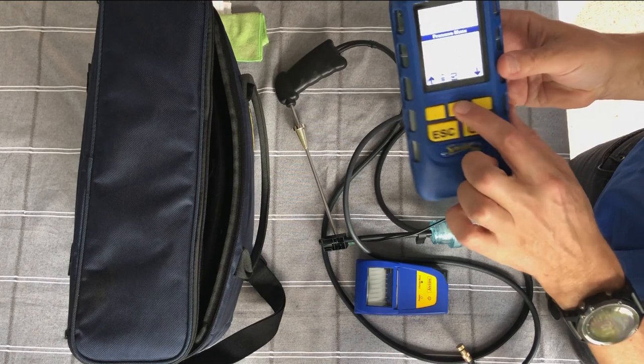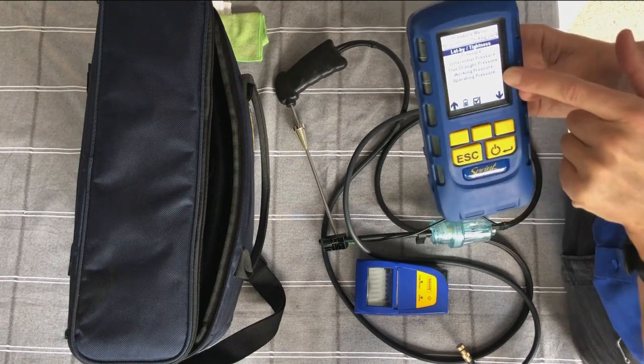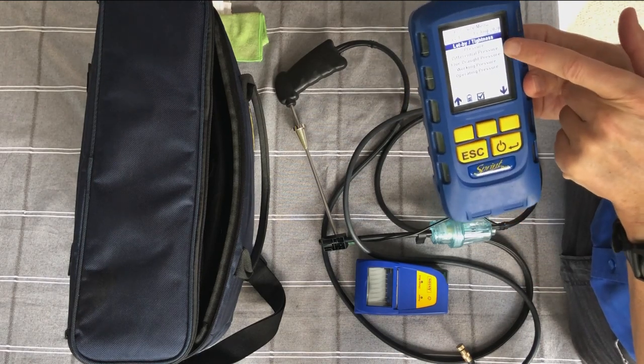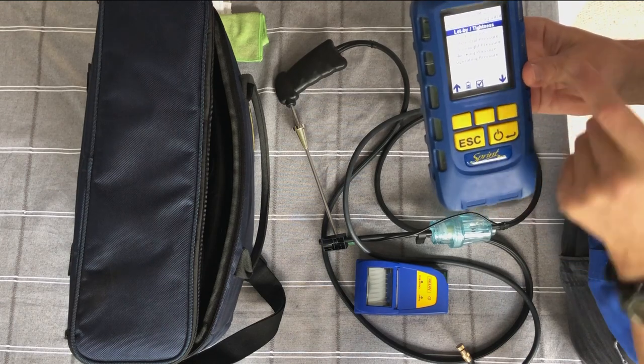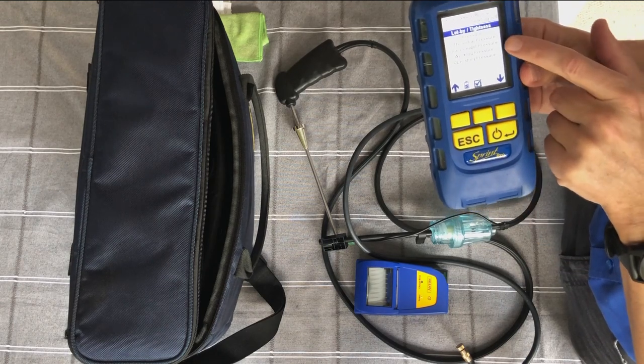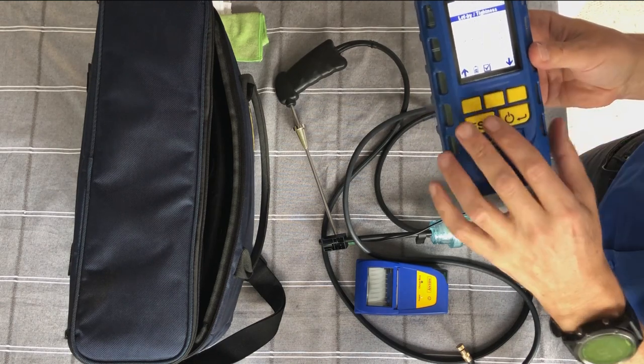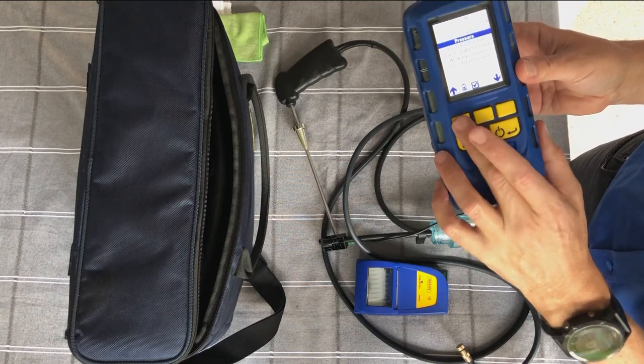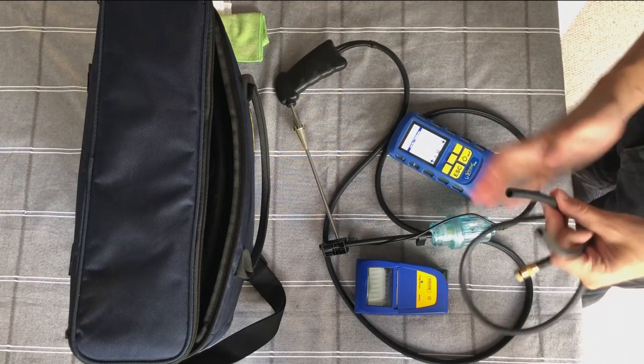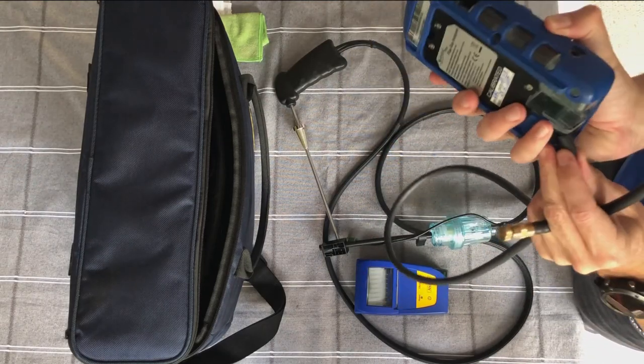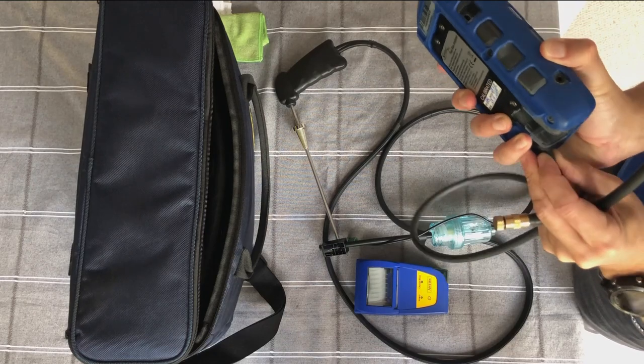Pressure menu. So again, if I press the tick to go into it, I've got different pressures that I can do here. Let-by tightness test, just take a pressure reading, differential pressure, draft pressure, working pressure, operating pressure. So again, up and down to select the one I want. Let's run through a let-by tightness test. So let's put this on the positive pressure spigot.